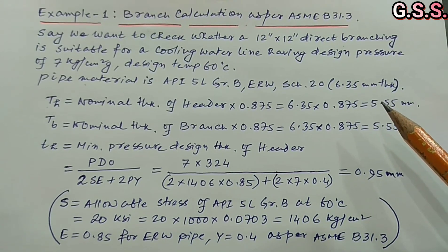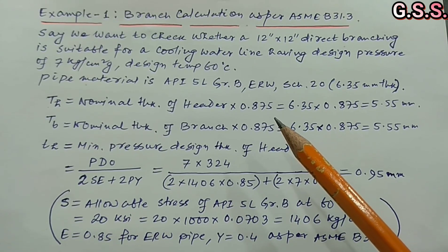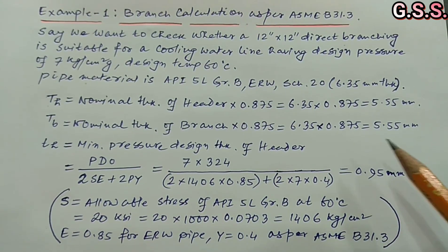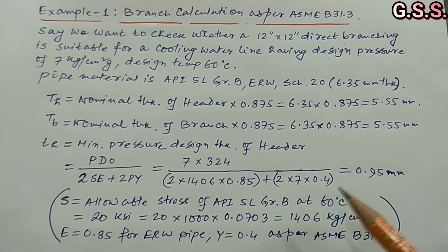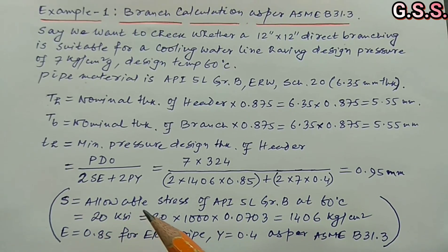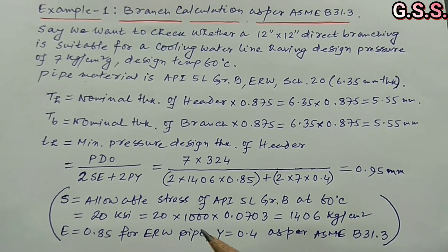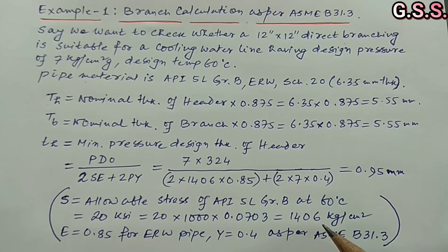Pipe material is API 5L Grade B ERW Schedule 20, that means 6.35 mm thick. Capital TH equals nominal thickness of header × 0.875 (considering 12.5% negative manufacturing tolerance) = 5.55 mm. Capital TB = nominal thickness of branch × 0.875 = 5.55 mm. Small tH = minimum pressure design thickness of header = P·D₀ / (2·S·E + 2·P·Y) = 0.95 mm. S = allowable stress of API 5L Grade B at 60°C = 20 KSI = 20 × 1000 × 0.0703 = 1406 kg/cm².